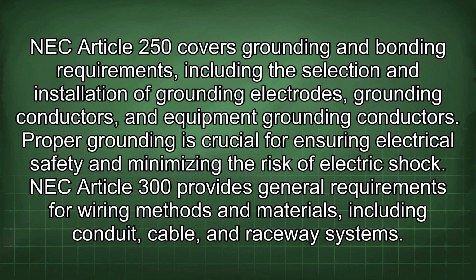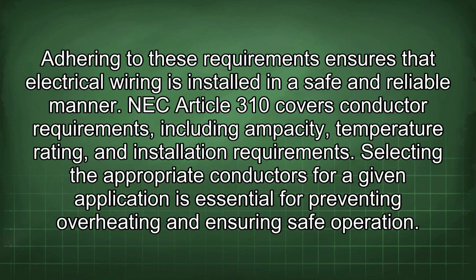NEC Article 250 covers grounding and bonding requirements, including the selection and installation of grounding electrodes, grounding conductors, and equipment grounding conductors. Proper grounding is crucial for ensuring electrical safety and minimizing the risk of electric shock. NEC Article 300 provides general requirements for wiring methods and materials, including conduit, cable, and raceway systems. Adhering to these requirements ensures that electrical wiring is installed in a safe and reliable manner.